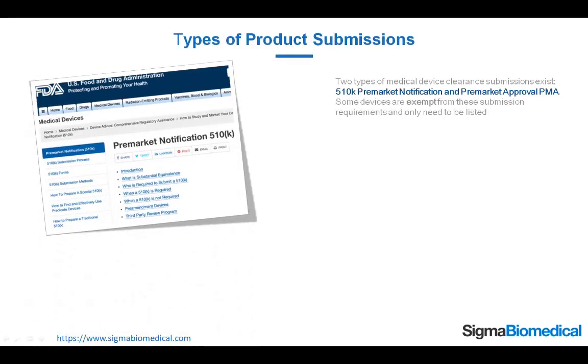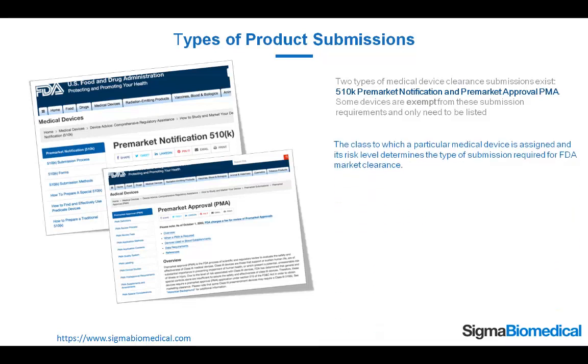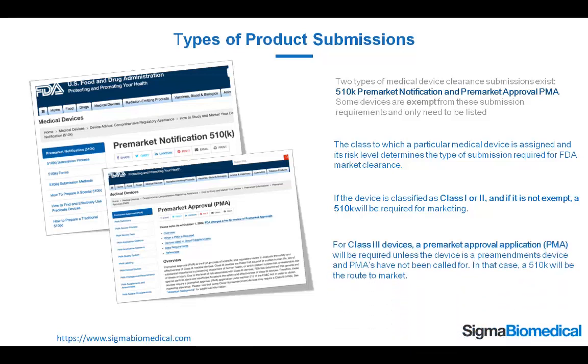Types of Product Submissions. Two types of medical device clearance submissions exist: 510k Pre-Market Notification and Pre-Market Approval (PMA). Some devices are exempt from these submission requirements and need only to be listed. The class to which a particular medical device is assigned and its risk level determines the type of submission required for FDA market clearance. If the device is classified as Class 1 or 2, and if it is not exempt, a 510k will be required for marketing. For Class 3 devices, a pre-market approval application will be required unless the device is a pre-amendments device and PMAs have not been called for — in that case, a 510k will be the route to market.